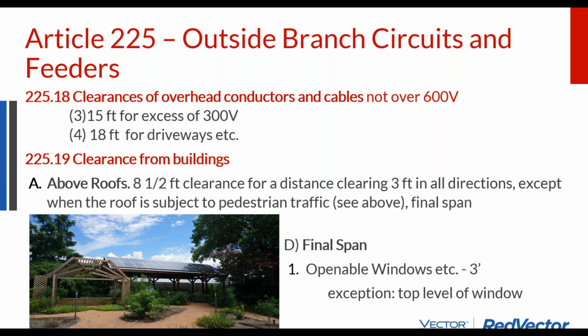Clearances for overhead conductors: 15 feet for over 300 volts, 18 feet or more for driveways. Above rooftops, an 8.5 foot clearance, except when the roof is subject to pedestrian traffic, where you get back to the above section. So when you're trying to design a covered rooftop deck with solar, what your code is saying is that for those wires, first off, you might not want to use the traditional 600 volt solar design format. You might want to use a 300 volt format to get a little bit of a lower patio covering or pergola, but it still needs to be 15 feet up in the air if you want people walking underneath those power lines.